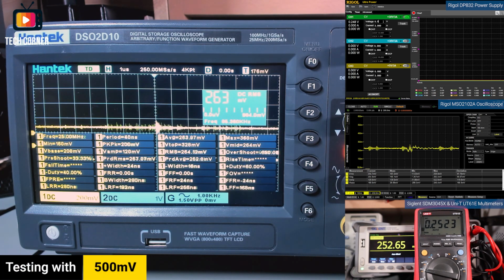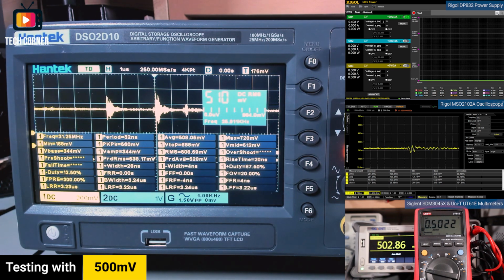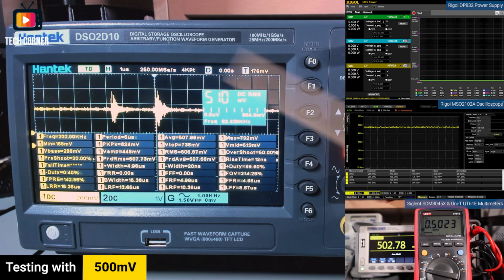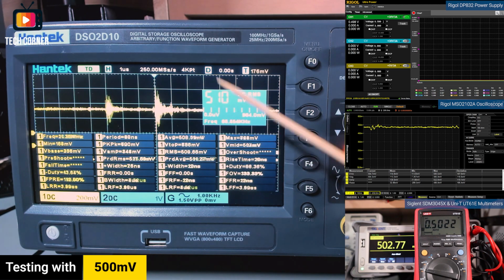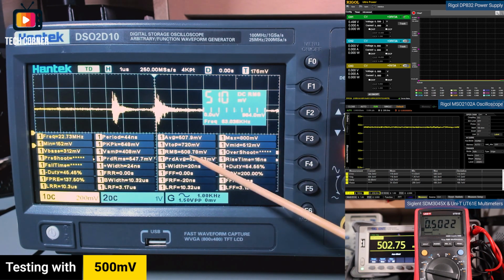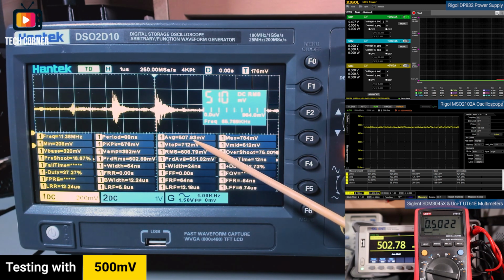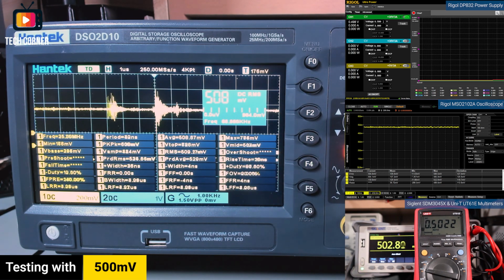I'm doing quite low voltage testing because that was one of the main issues. As you can see, changing the voltage without the auto set, it gives me 510 on the voltmeter. It's about the same on average and RMS. On average we have 507.8. On the multimeters we have 502. This one 502 also, 0.2, 0.7, so the difference is negligible. And on the Rigol we have 505 on VRMS, and also on average 504, 505. So we still have a 3 millivolts difference between the multimeters and the Rigol.